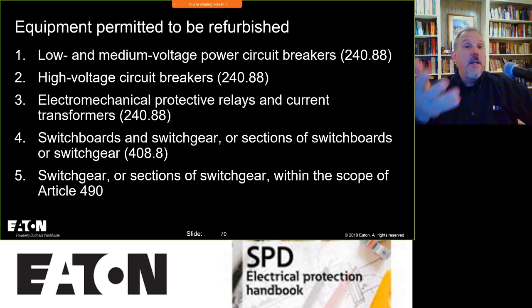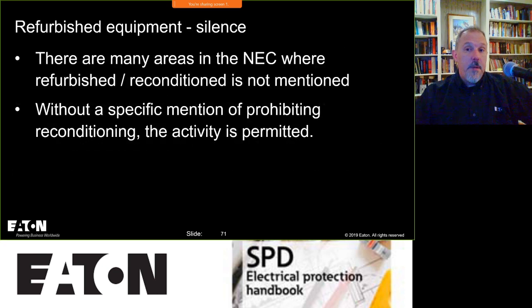Some local jurisdictions, like Shelby County, Alabama, I know the inspector there will tell me, not in Shelby County, Alabama. It ain't happening here, because they require that listing mark on a lot of things above and beyond what the National Electrical Code requires. So be mindful of that, that when you remove that mark, that's part of some of the pushback. You may have to show, or do a little field evaluation or something of that nature, based upon the inspector's position on that.